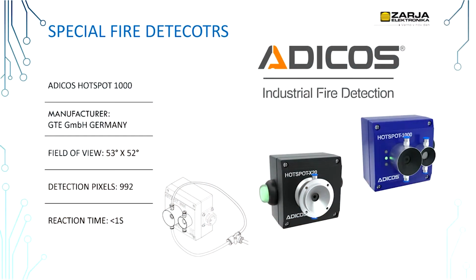And when we checked all those spots with the customer, we decided to go with Adicos special fire detectors, Hotspot basically. They are from the German manufacturer GTE and are very good for harsh environments. They can detect temperature on a surface with a rate of temperature rise. How should I call it?